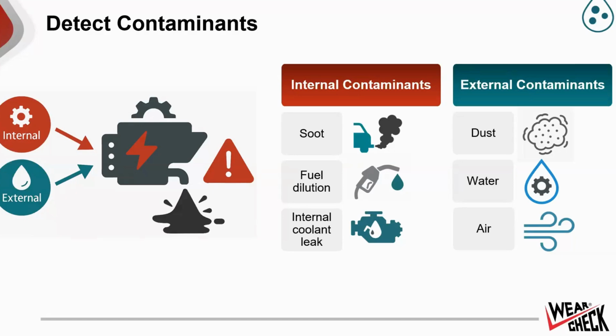Soot raises the oil's viscosity. It accelerates oxidation. It depletes additive. It's also very abrasive. Internal coolant leaks, especially when the coolant contains glycol, that can increase the viscosity. It can trigger oxidation. It causes acid formation and usually corrosive wear of bearings.